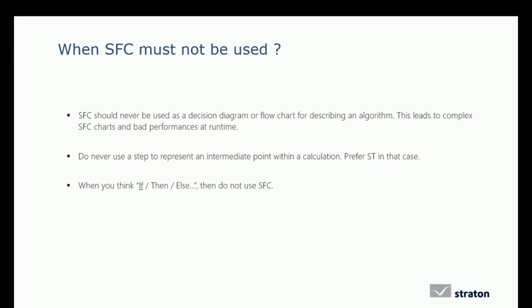So now, when must we not use it? The SFC should never be used as a decision diagram or flowchart for describing an algorithm. This leads to complex SFC charts and bad performances at runtime. Never use a step to represent an intermediate point within a calculation. Prefer the ST language in that case. Generally, when you think if, then else, then do not use the SFC.